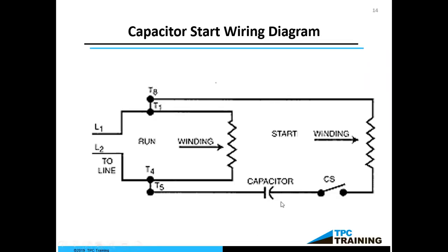And we would be using the capacitor for a couple of things. One, the capacitor is going to charge up to the peak of the sine wave. So if I'm using 120 volts for this single-phase motor, the capacitor is going to charge up to 170. That's going to help me start this motor a little bit more efficiently. Plus, by putting the capacitor in the circuit, it gives me a little bit of a phase shift, and that phase shift helps me with rotation on a single-phase motor.